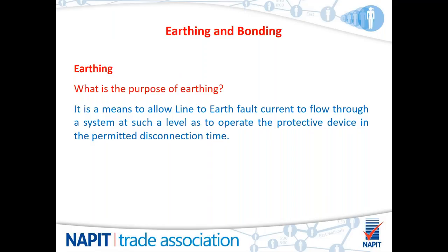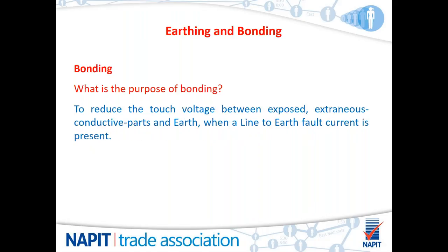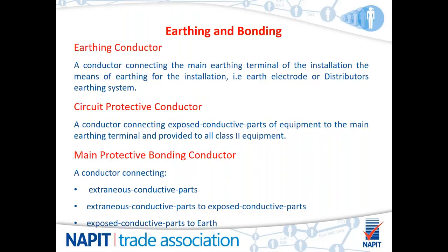Right, so earthing then. What is the purpose of earthing? Essentially, it is a means to allow line to earth fault current to flow through a system at such a level as to operate the protective device within the permitted disconnection time. Totally different to bonding, because bonding is there to reduce the touch voltages between exposed and extraneous conductive parts and earth when a line-to-earth fault is present. A lot of these terminology references will be made clearer as we go through.